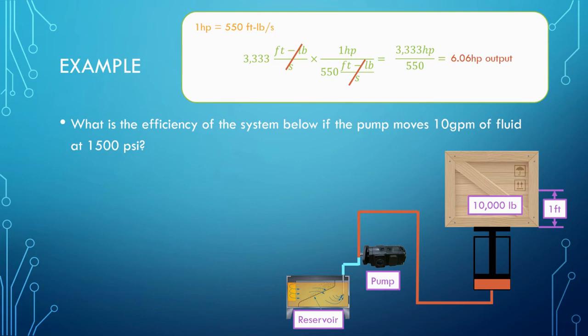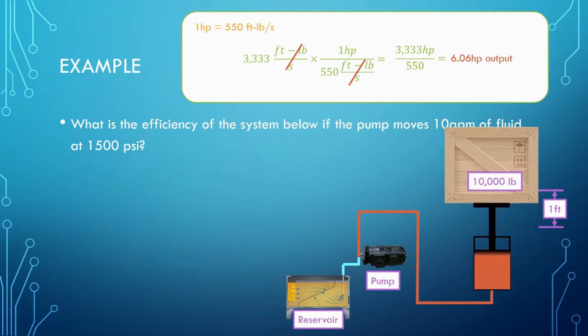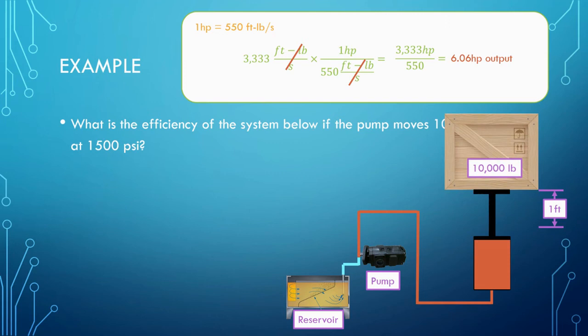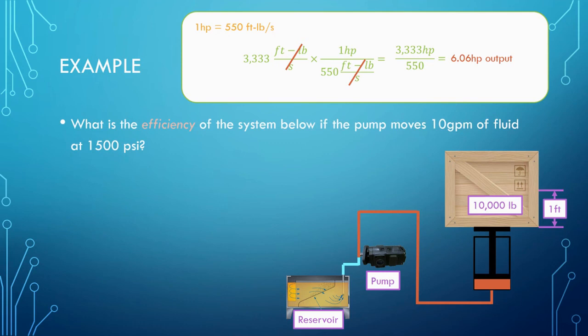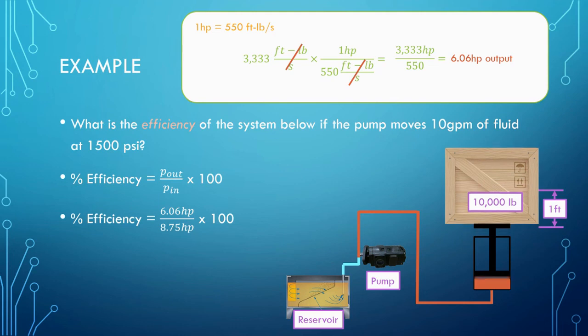What is the efficiency of the system if the pump moves 10 gallons per minute of fluid at 1500 psi? To find the efficiency of the system, we have to compare the output power with the input power. The input power can be calculated using the rate of flow 10 gallons per minute and the pressure 1500 psi. 10 times 1500 divided by the horsepower constant 1714 equals 8.75 horsepower supplied by the input. The percent efficiency can be found by dividing the output power by the input power and multiplying the result by 100. 6.06 horsepower divided by 8.75 horsepower times 100 equals an efficiency of about 69%.